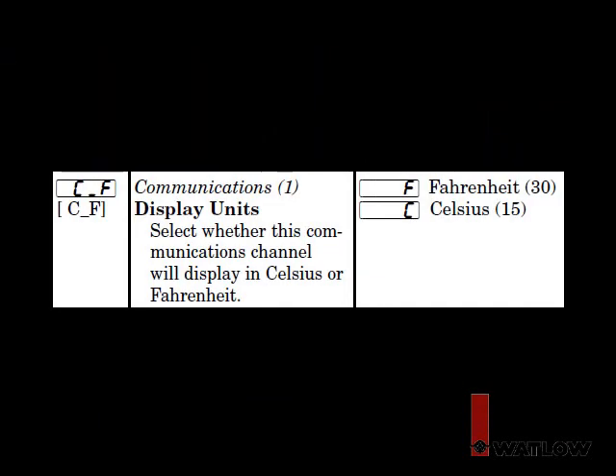To change the serial or Ethernet communications to transfer data in the units of choice, either write to a memory location within the EZ-ZONE or change the display units in the setup page communications menu. The write value sent is either 30 for degrees Fahrenheit or 15 for degrees Celsius. The instance of which memory location to write is based on the communications port of the controller having the non-standard bus protocol — communications port 1 will be instance 1 and communications port 2 will be instance 2. The method to perform a write will vary based on the available protocol. Please refer to the user's manual for the appropriate memory location or register.